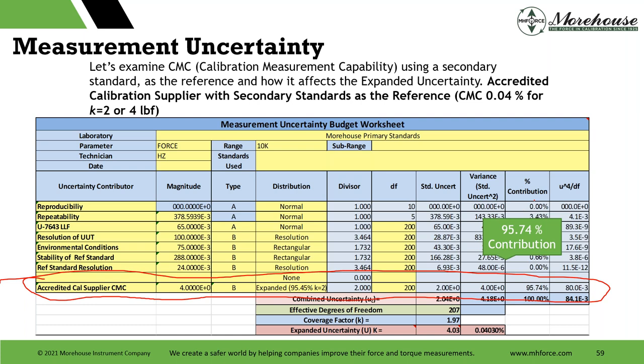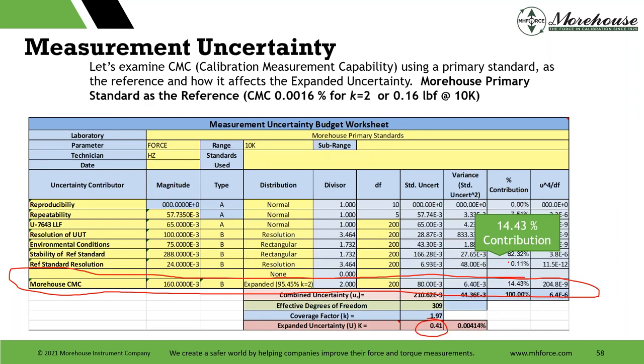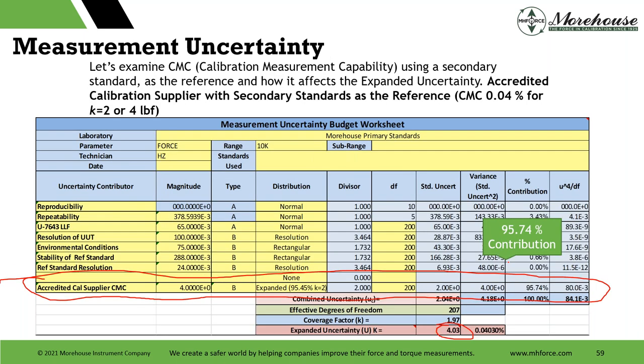95.74% of our budget, and instead of 0.41, it's 4.03. So basically, you're absorbing all of the uncertainty, whether you like it or not. Whoever you use to perform your calibration, the best they can do, you cannot be better than. And in the case of primary standards dead weight that we looked at here, there's other percentage contributions like stability and stuff that are more dominant. You would get an expanded uncertainty from us of 0.41 with that load cell versus an accredited supplier using secondary standards is going to come out to be about 4 pounds.